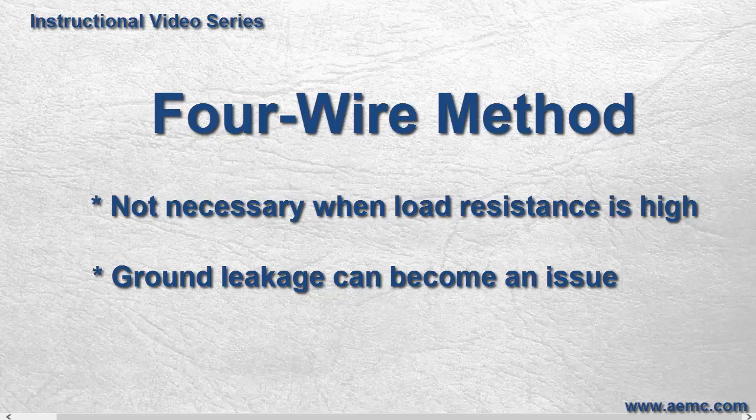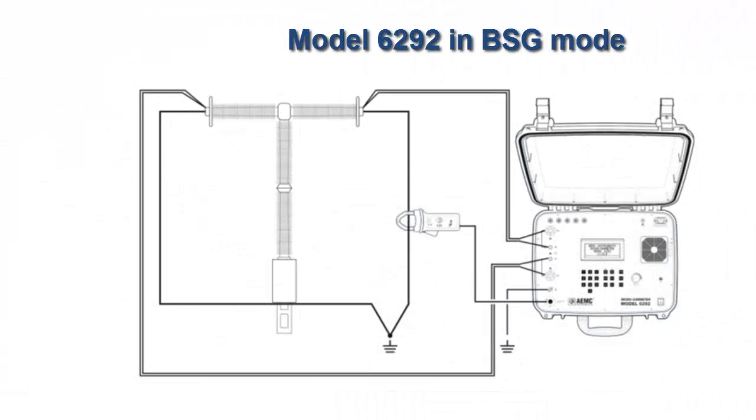The Model 6292 mitigates the problem of ground leakage by offering a mode called Both Sides Grounded, or BSG mode. In this mode, the Model 6292 uses an external DC current probe to measure and eliminate ground leakage current from the total test current.